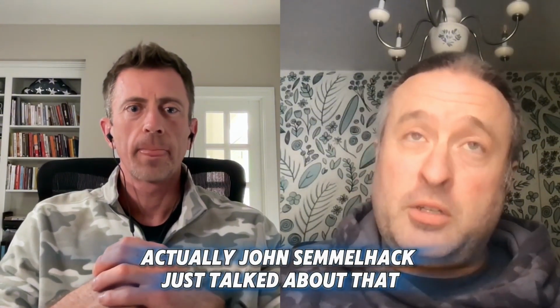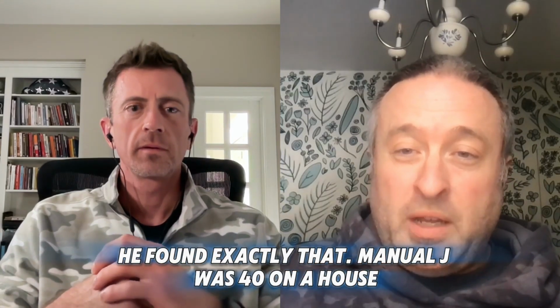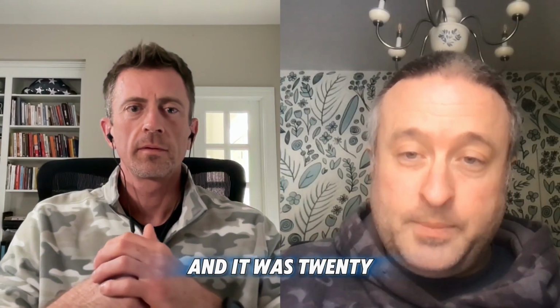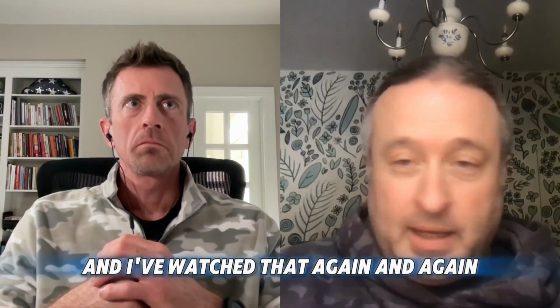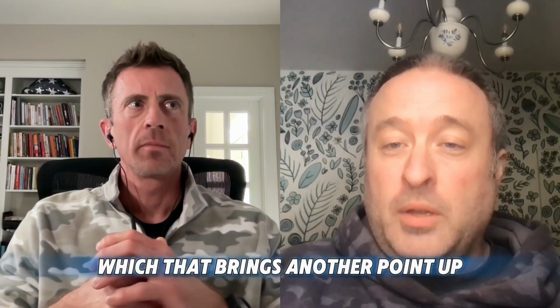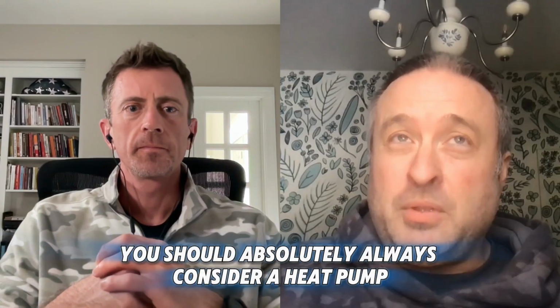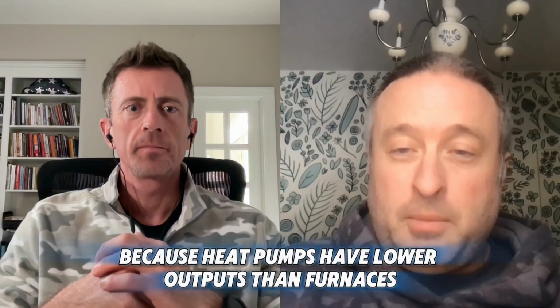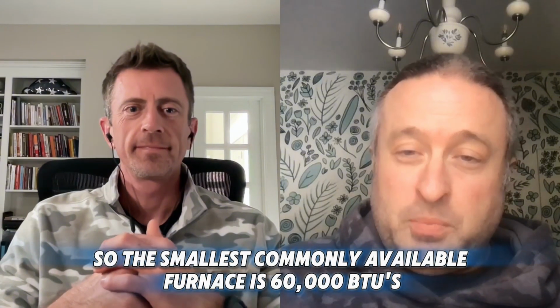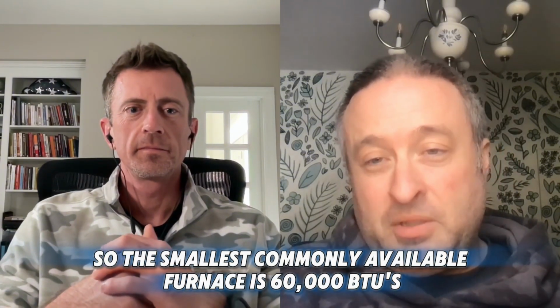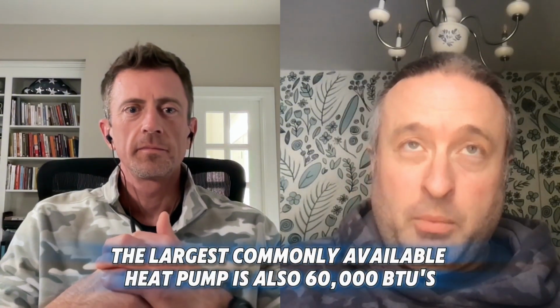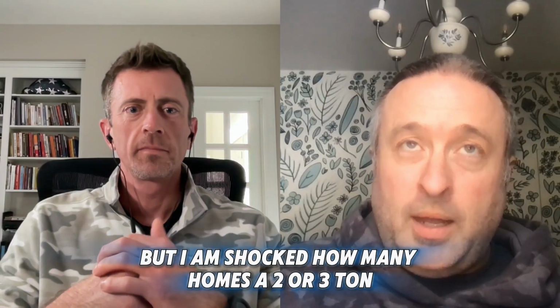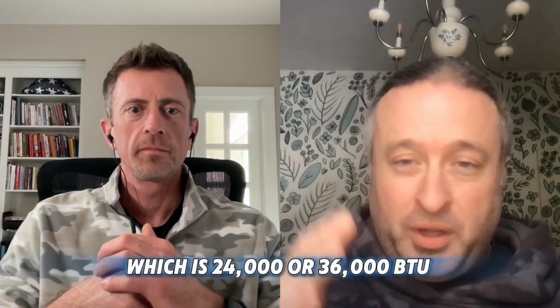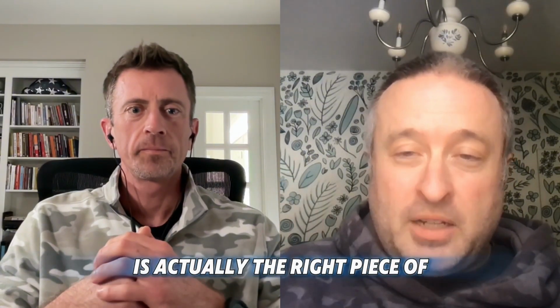Actually, John Semmelhack just talked about that down in Florida at the HVAC symposium. He found exactly that. Manual J was 40 on a house, and he watched the actual runtime, and it was 20. And I've watched that again and again and again, which brings another point up. You should absolutely always consider a heat pump, because heat pumps have lower outputs than furnaces. So the smallest commonly available furnace is 60,000 BTUs. The largest commonly available heat pump is also 60,000 BTUs. But I am shocked how many homes a 2 or 3 ton, which is 24,000 or 36,000 BTU heat pump, is actually the right piece of equipment.